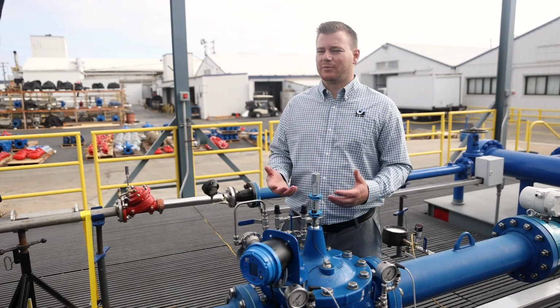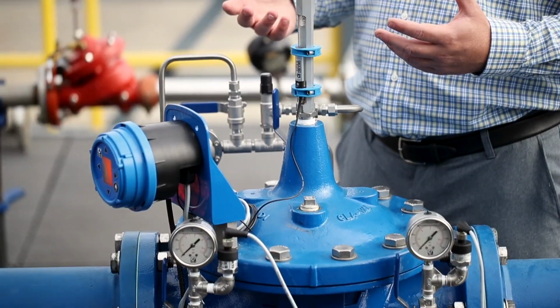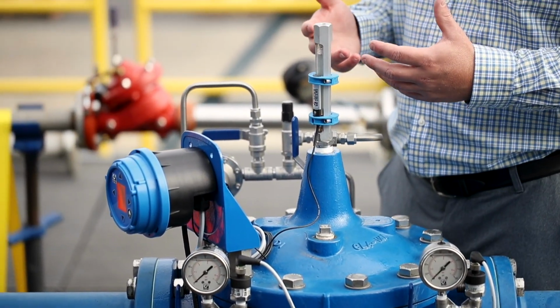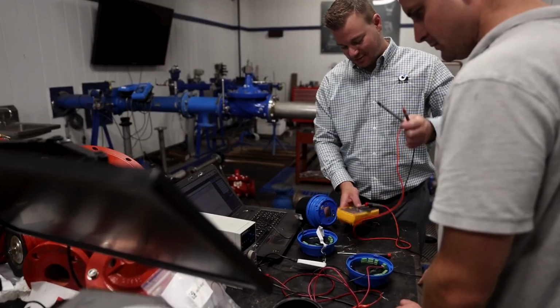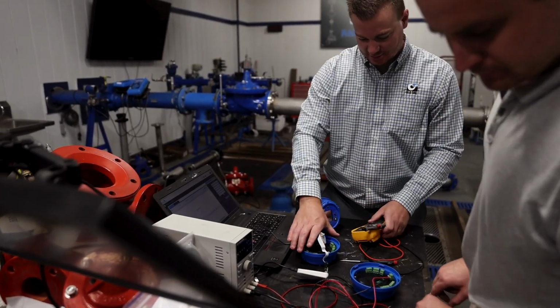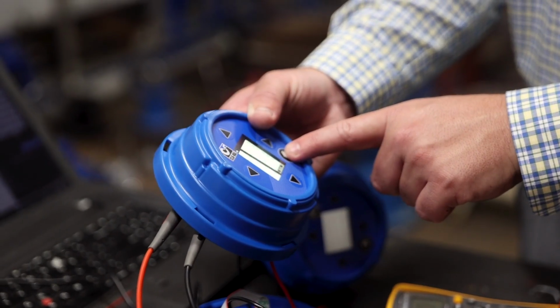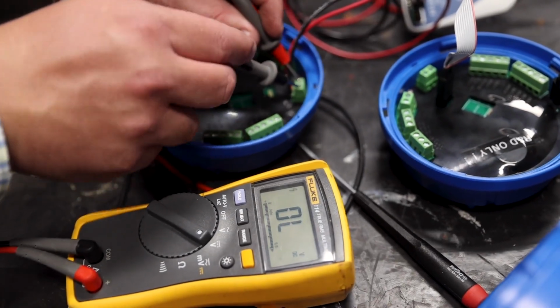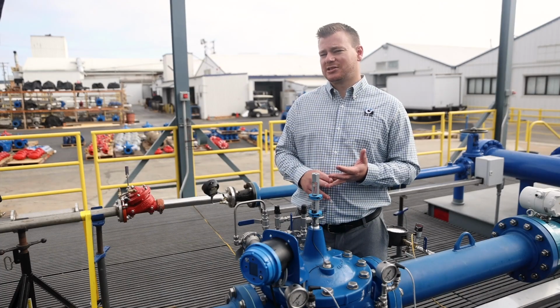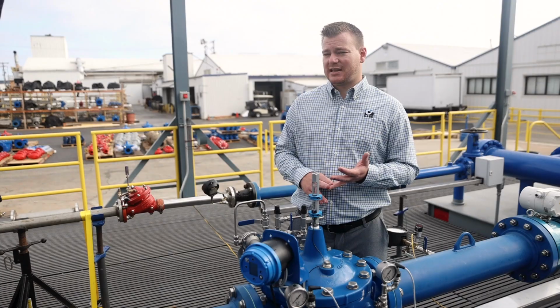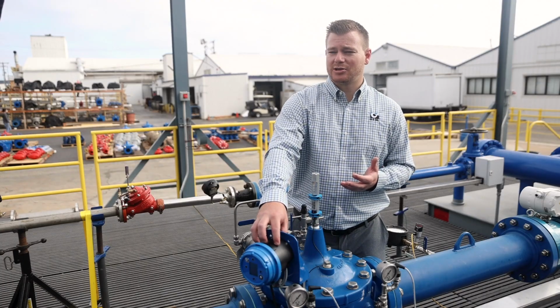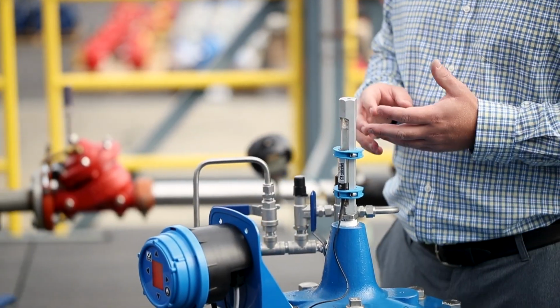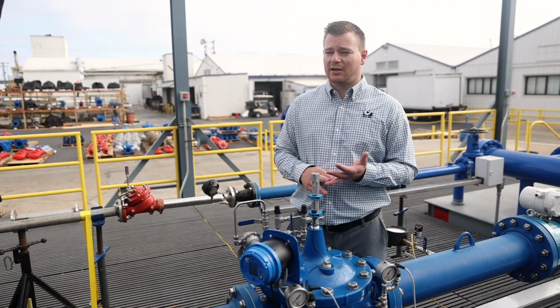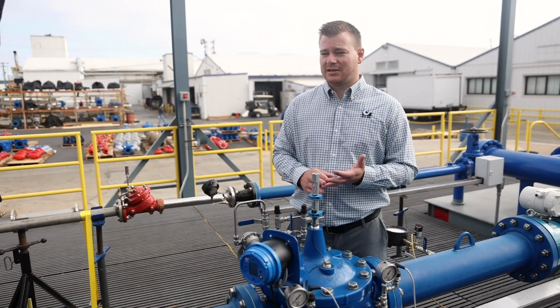So besides the X35 being thought of as something that calculates and measures flow, you can also think of it as a data logger or instrumentation acquisition module. There are 4 analog inputs and 4 analog outputs, which allow us to take the position and pressure readings, but we could also bring in additional field devices into the module. It also has an SD card, which allows for data logging as well as retransmitting to your SCADA system.